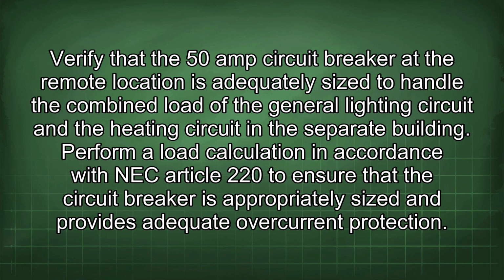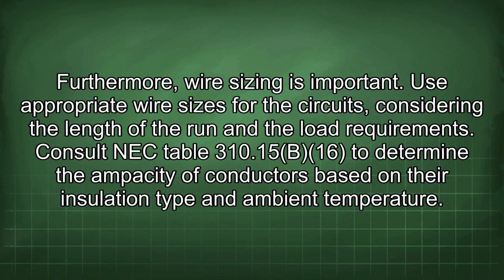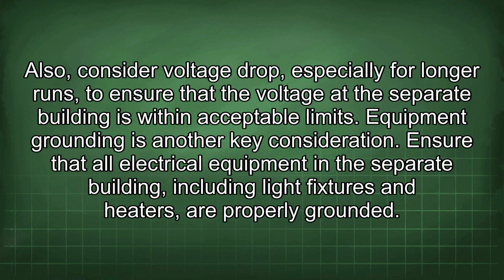Perform a load calculation in accordance with NEC Article 220 to ensure that the circuit breaker is appropriately sized and provides adequate overcurrent protection. Furthermore, wire sizing is important. Use appropriate wire sizes for the circuits, considering the length of the run and the load requirements. Consult NEC Table 310.15(B)(16) to determine the ampacity of conductors based on their insulation type and ambient temperature. Also, consider voltage drop, especially for longer runs, to ensure that the voltage at the separate building is within acceptable limits. Equipment grounding is another key consideration.